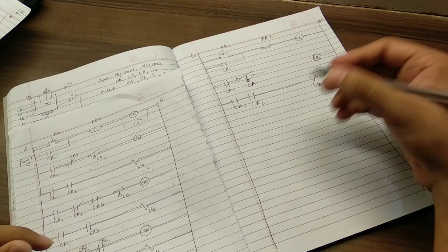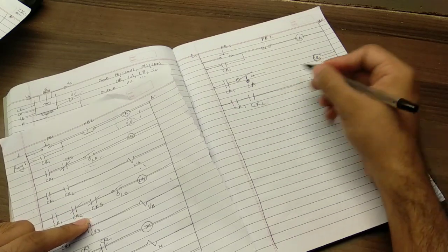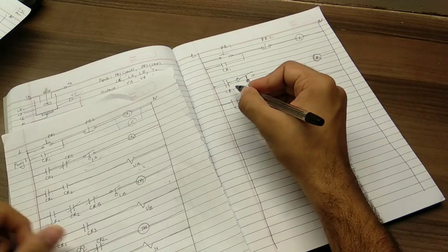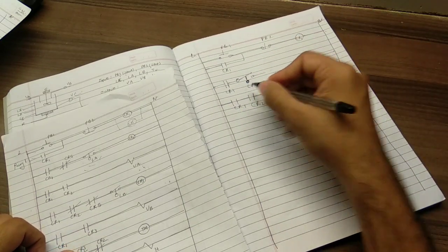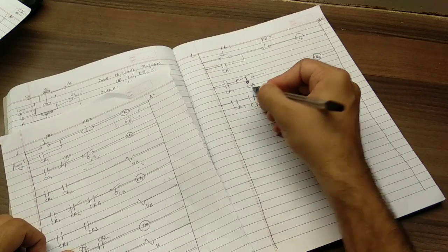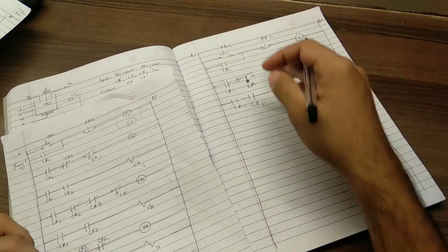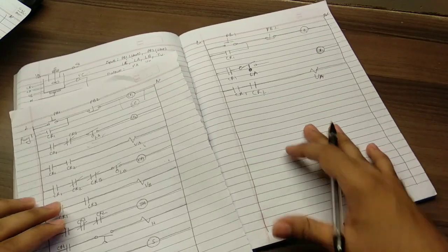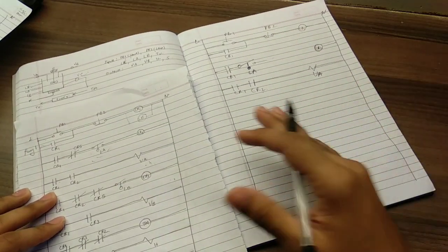The criteria for actuation of valve A is basically CR2 being on, and the criteria for CR2 being on is that CR1 has to be on, and the water level should be below LA. If the water level is above LA, CR2 would be off. Other conditions would just add up, as those are AND conditions. If you have OR conditions, you can add them, but I don't think in this problem statement we have any OR conditions.